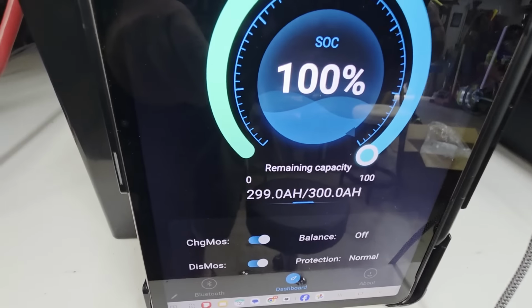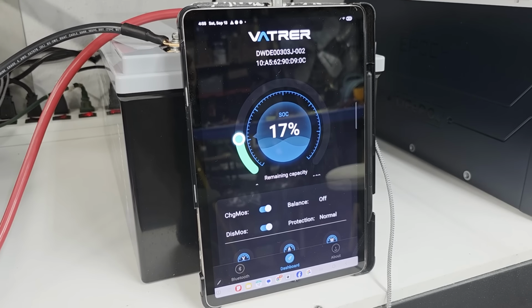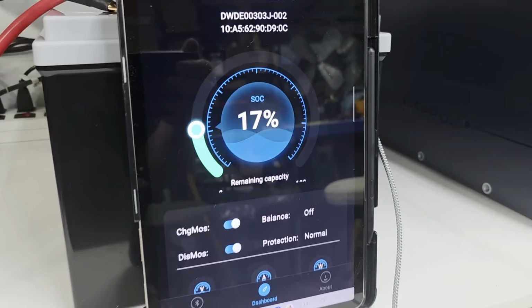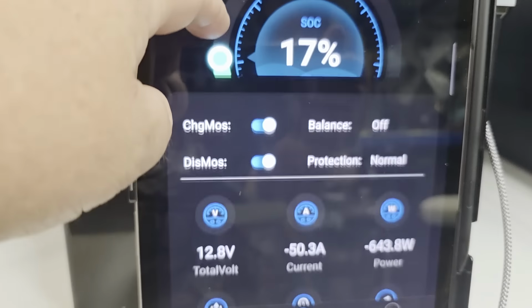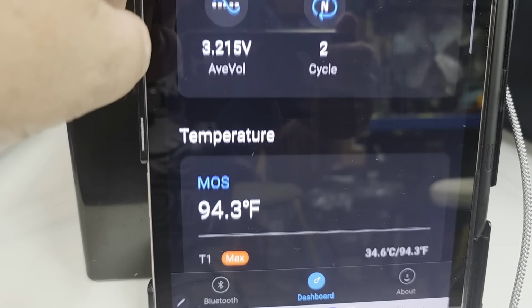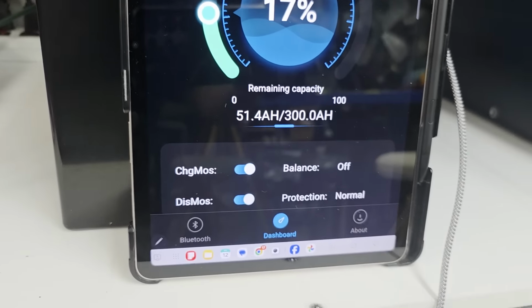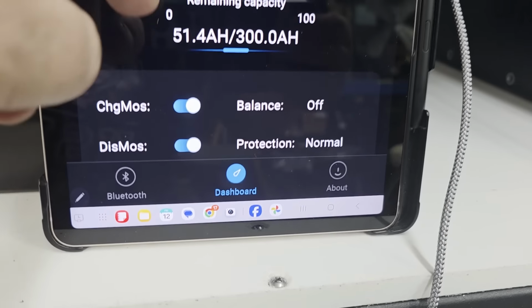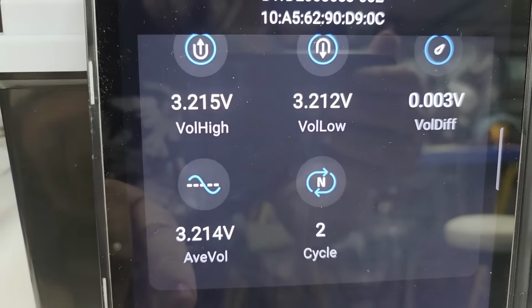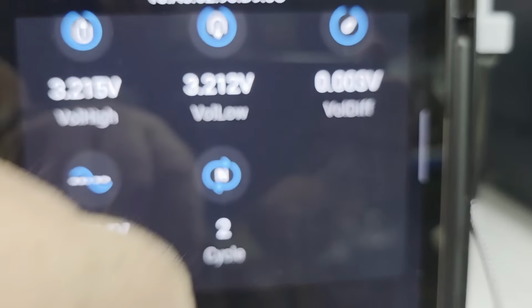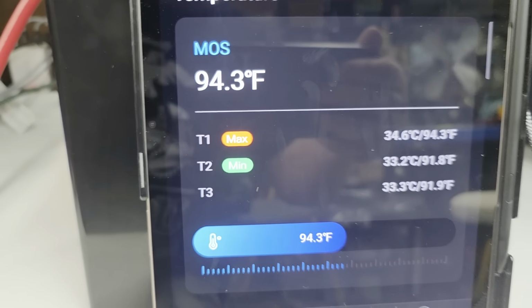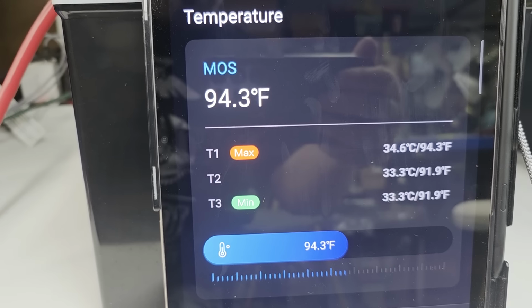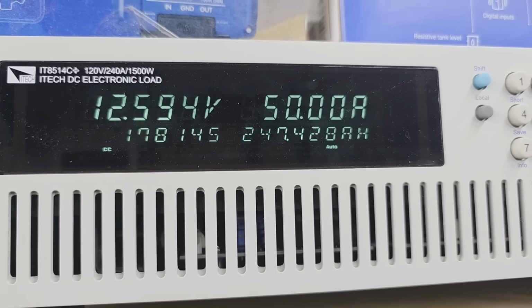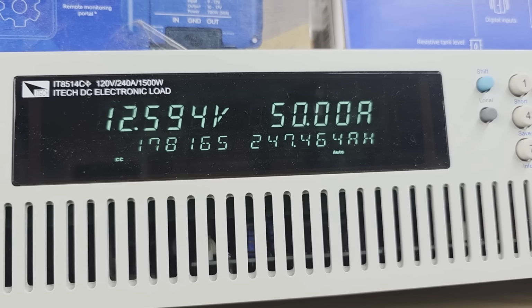We'll let it go, I'm just about ready to cross 1 amp hour already. We'll come back and check this when it's done. There we go, 299 amp hours. Alright, still continuing the test, just checking in. Down to 17% SOC, 51.4 amp hours left of 300. We're not anywhere near the lower knee, so cell balance is still very good. MOSFET temperature is a little elevated because it's kind of hot in here and it's got a 50 amp load on it. The test equipment has settled at exactly 50 amps for quite some time.